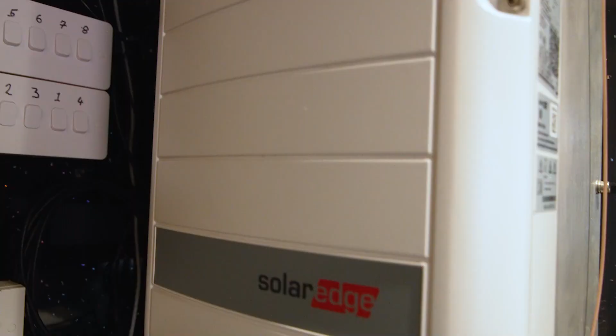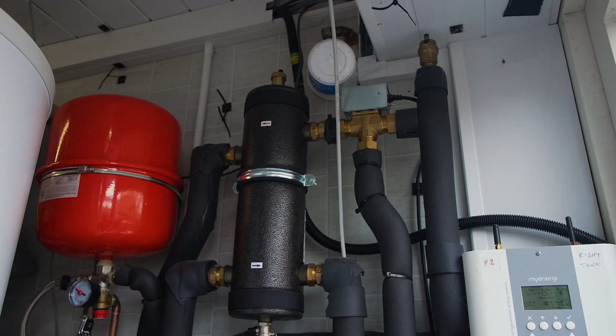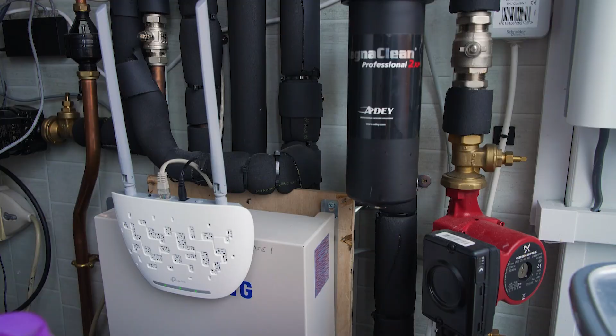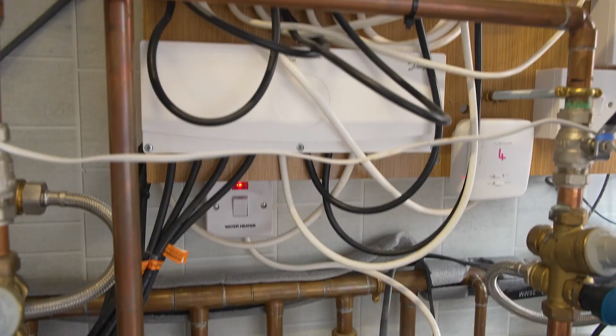Had the manifold custom made - this was in view of a gas setup, and I specifically wanted each room to be zoned. Then I watched your video, and rather than switching rooms on and off, I now have the ground floor permanently heated, the first floor permanently heated. I took the flow temperature from 55 down to 40, and I was really fortunate in being able to put the heat pump right on the other side of the wall there, so it's a really short run.